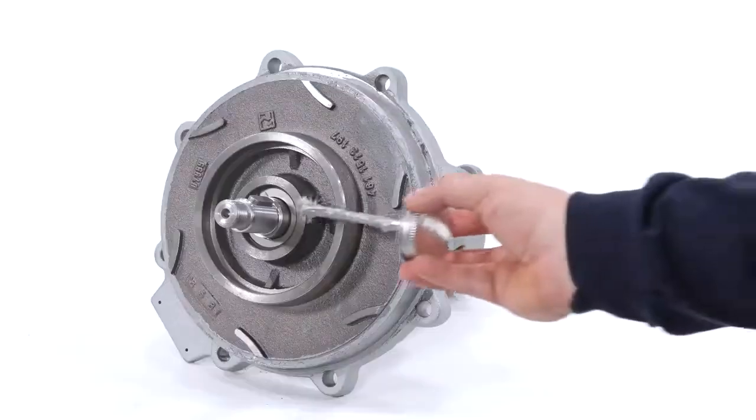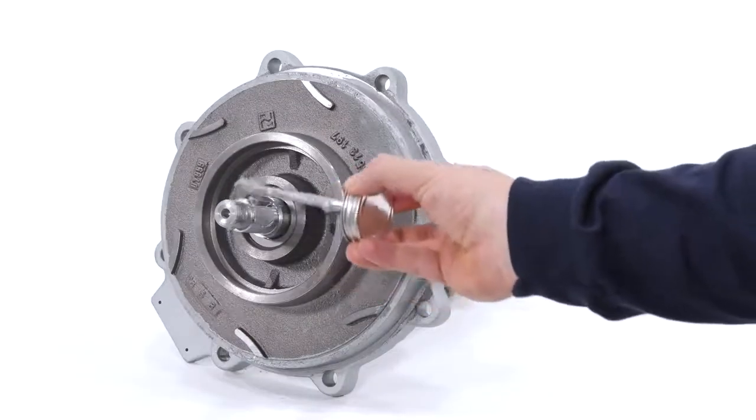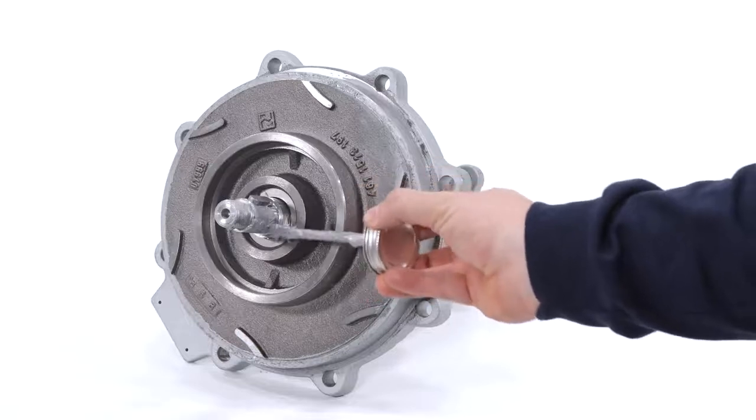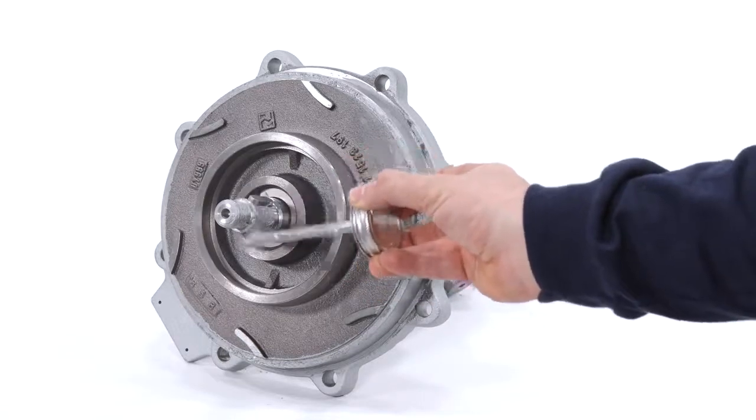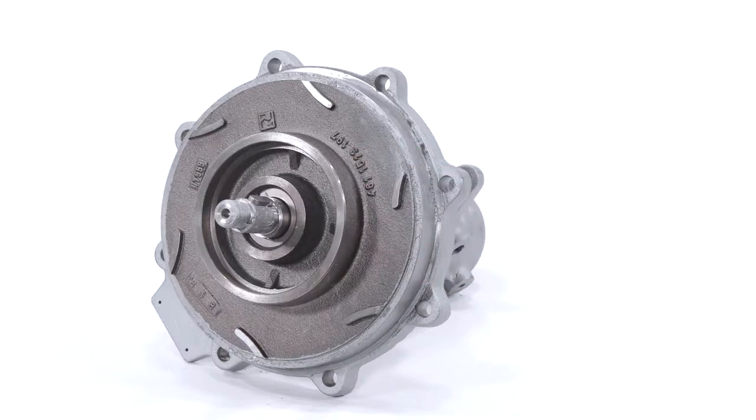We recommend that you apply an anti-seize lubricant to the drive shaft before installing the impeller. Other areas we recommend to use anti-seize lubricant are the mating surfaces of the casing and casing cover as well as both sides of the case gasket.